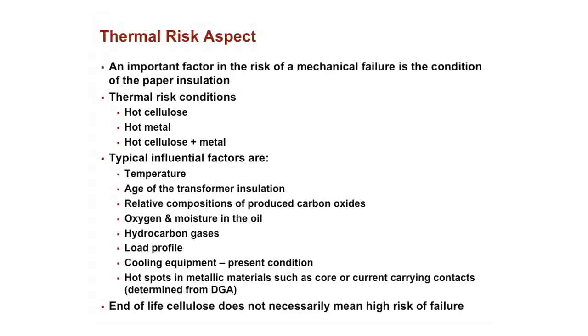What we look at here is a lot of DGA, and there are kind of three types of gassing that you look at. The first is hot cellulose. This is where you have just cellulose gassing, so carbon oxide gassing, and normally you actually have normal cellulose aging, and we don't worry about that so much. You also have hot metal gassing. This is where you have some kind of overheating, either in the core clamping system or in the tank, or could be in the clamps or something like that. And that too, we don't worry about so much either. This is more a nuisance gassing than anything. The worst thing though is when you have hot cellulose and hot metal. That means you have some hot spot where there's paper involved, and that's serious.